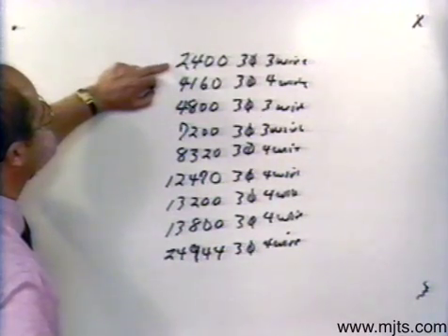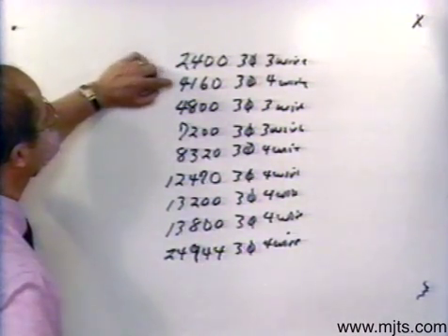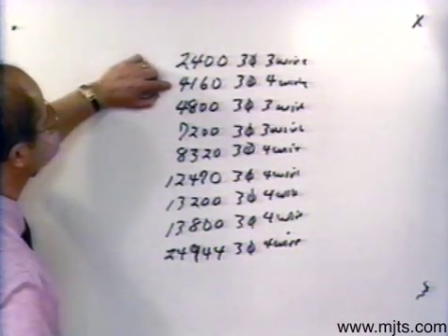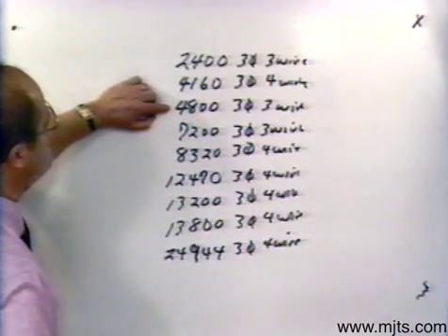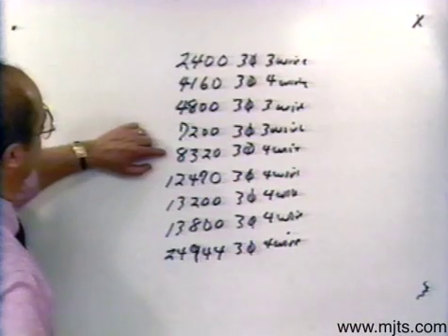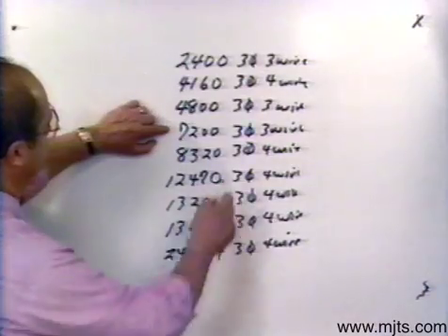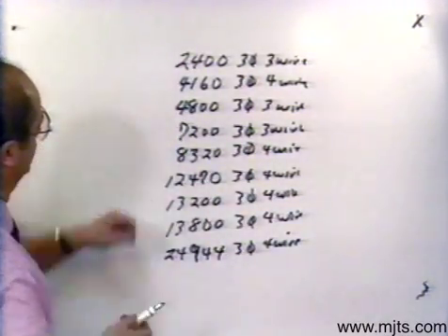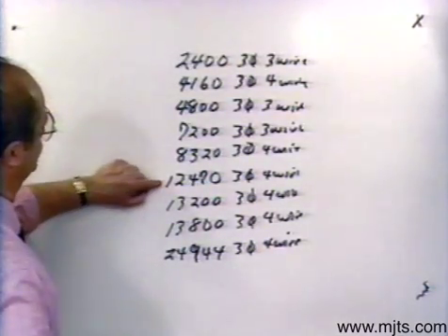Say for example, 2400. If I reconnect those, you see Y instead of delta, I would have a 4160 system. And you see that if I had 4800, that I reconnect that, I would have 8320. My 7200, if I would reconnect that from delta, which we've got here, to a Y. You would see that we would have 12470.